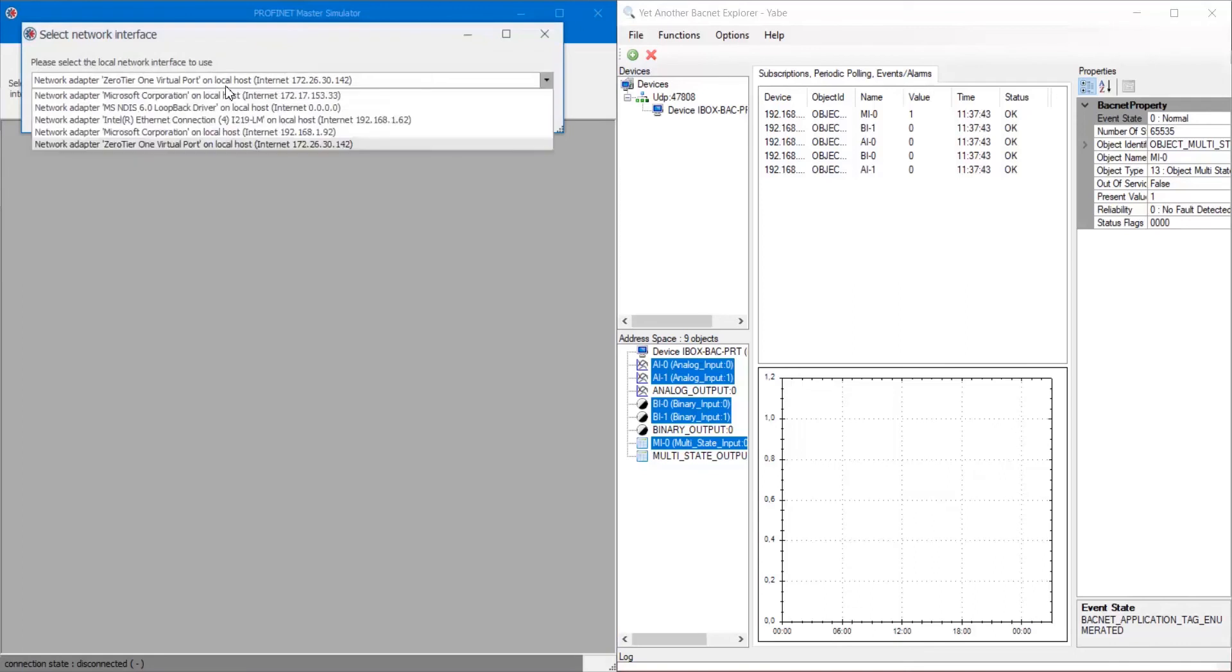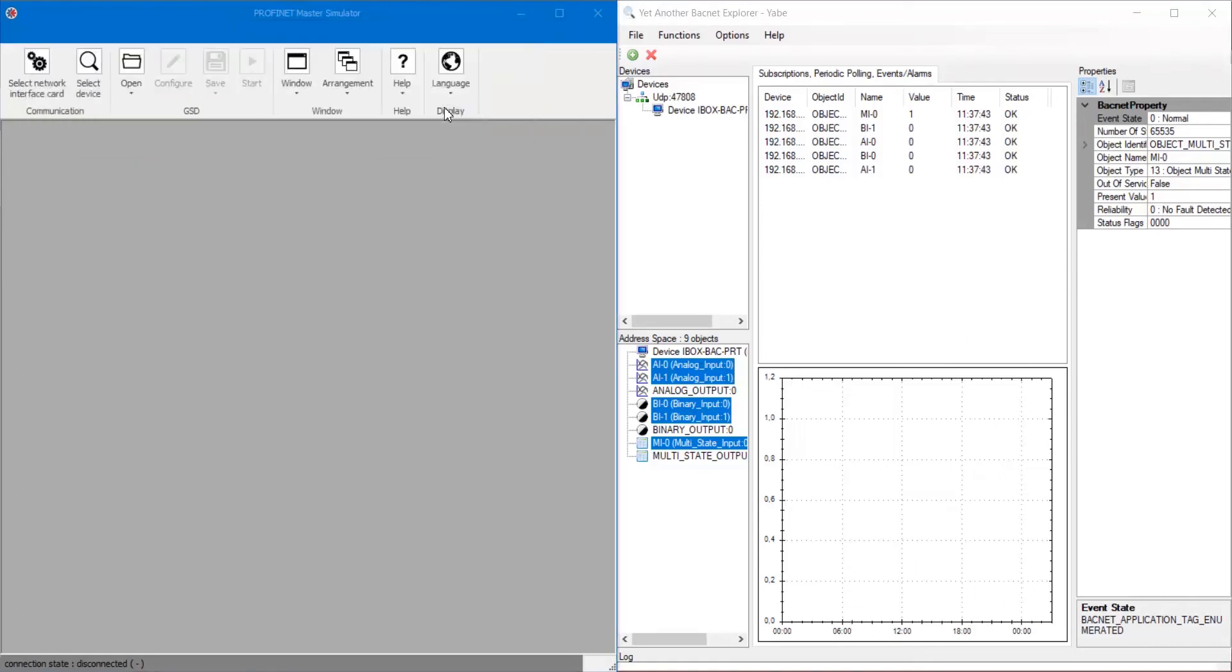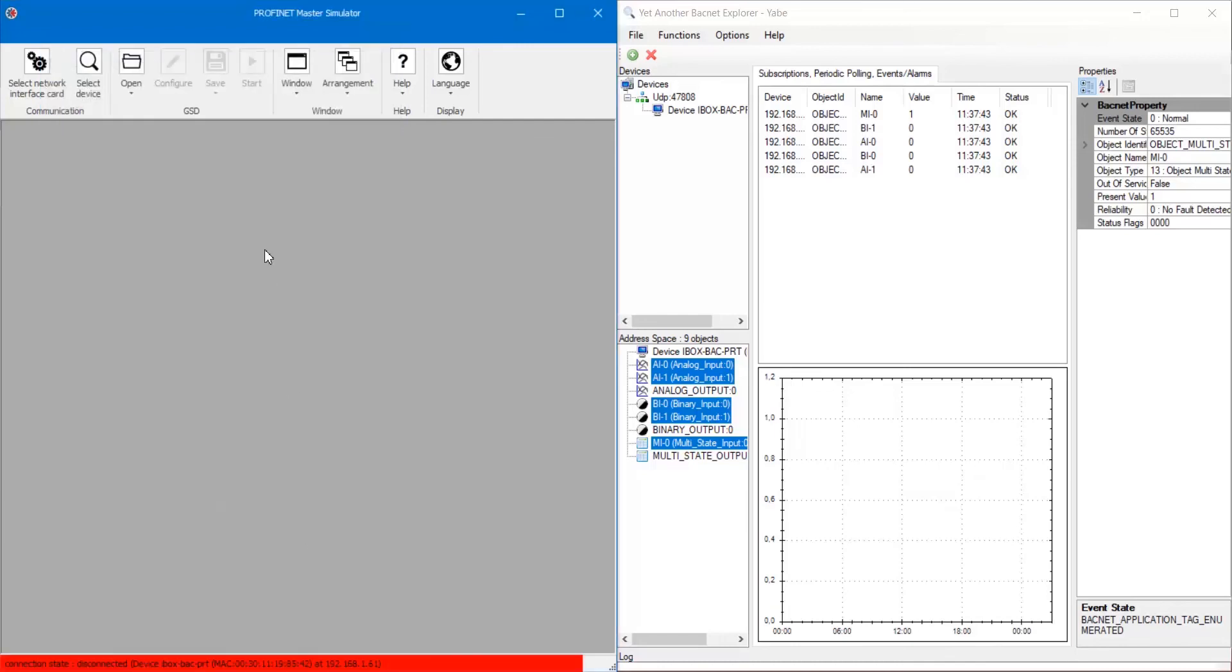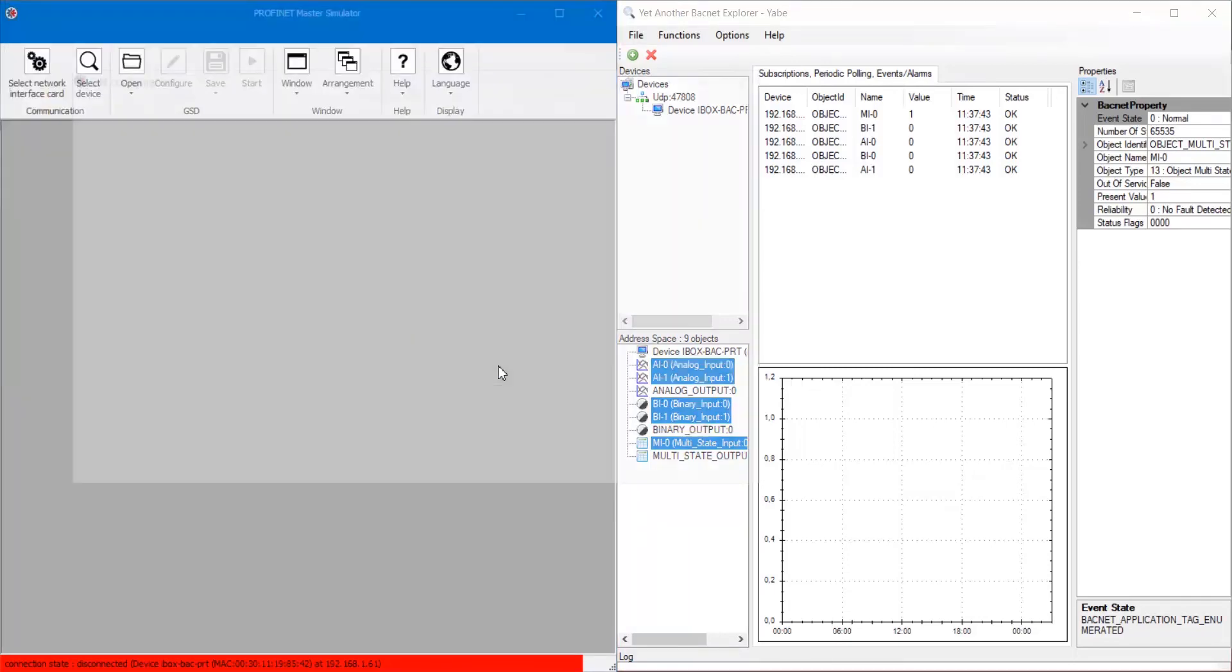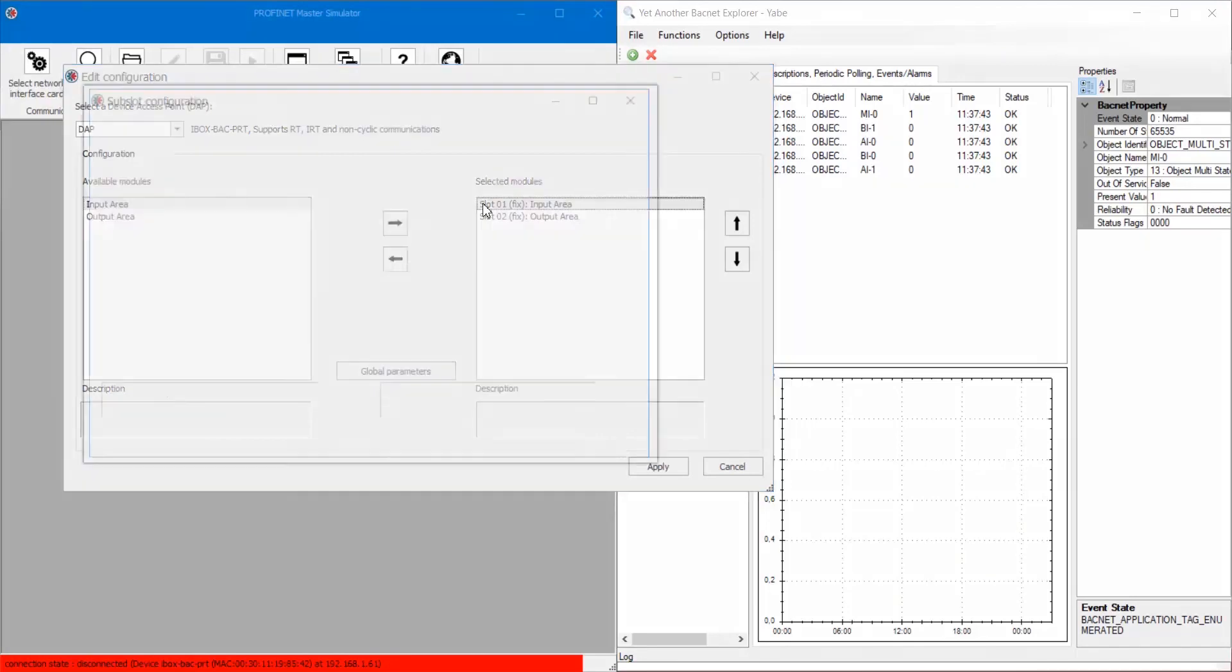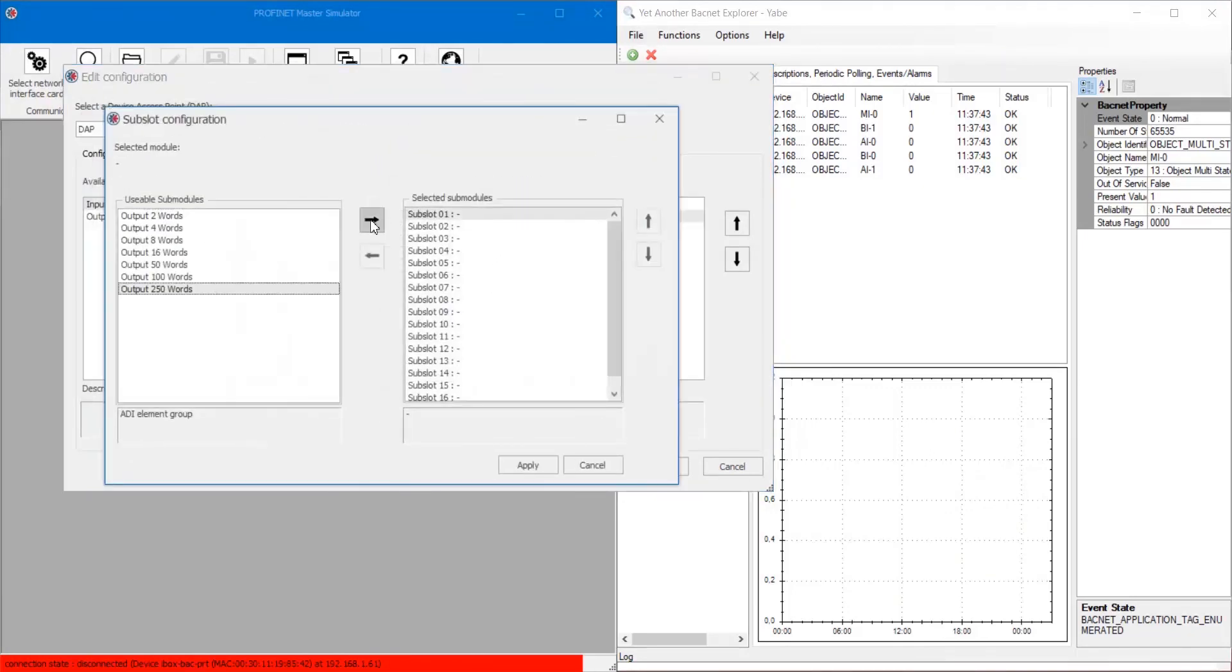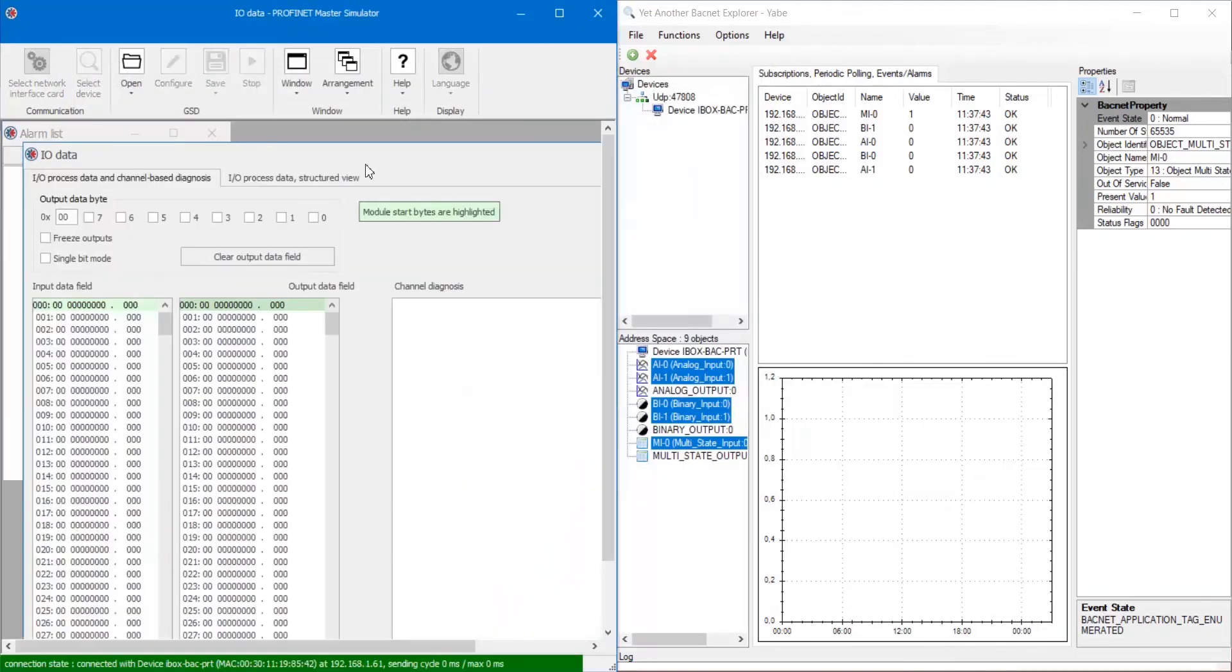On Profinet master simulator, select interface to be used and go to select device menu to select our gateway from the scan list. Now, select GSD file and configure IO data memory blocks. Then, click on start to initiate communication with the gateway.